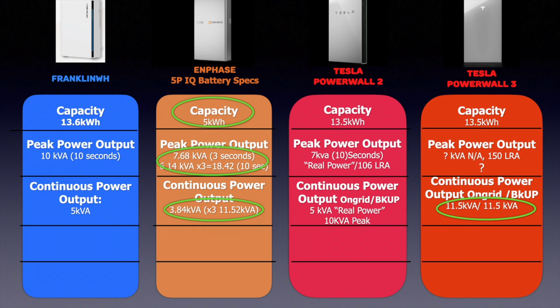So in this case, Enphase would be advantageous. Now let's talk about continuous power output - this is how much you can run continuously out of your battery. With the Franklin, it's 5 kVA. With the Enphase, if you're using 3 batteries, it's 11.52 kVA, so that's more than double the Franklin. The Tesla Powerwall 2 is 5 kVA real power, and they have 10 kVA peak - I don't know why they have that number there, but I'm using the real power number. And the Tesla Powerwall 3 has 11.5 kVA. So in this case, either 3 Enphase batteries or the Tesla Powerwall 3 is the best for this spec.